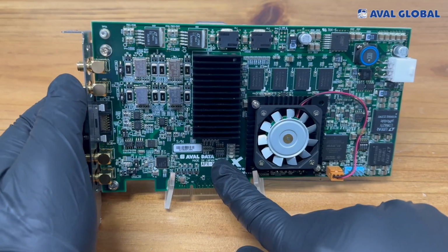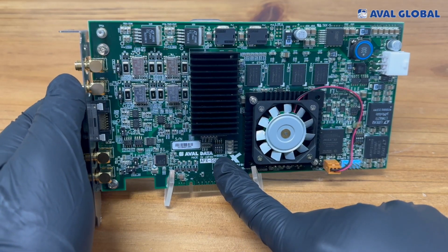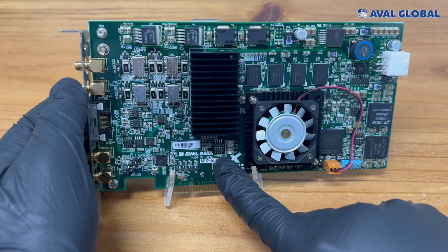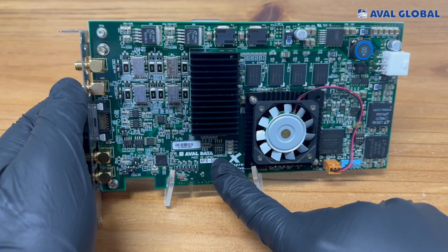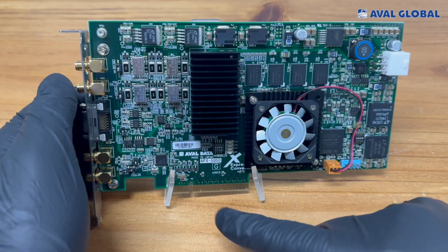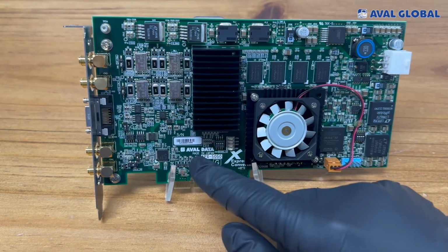Switch 3 is located on the left side of the heatsink and allows you to set the ID of the board. When using multiple ADC boards, set this switch differently for each. If the board IDs are the same, board recognition does not work properly.